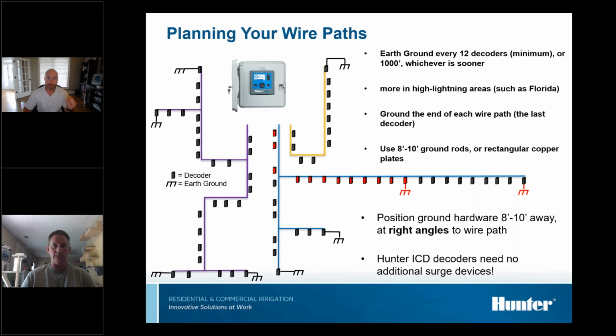Like I said, every 12 decoders or every 1,000 feet, you want to ground the end of each wire path. Like the example we just looked at before, if you've got multiple wire paths, at the end of every path, the last decoder you want to ground. And then you also want to ground every 12 decoders or every 1,000 feet.